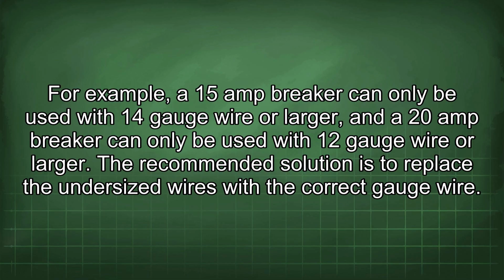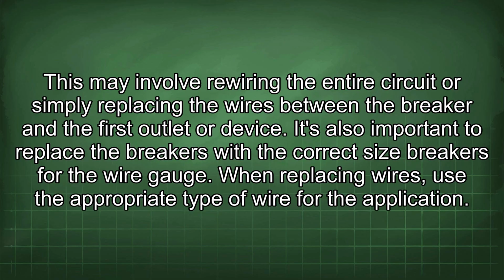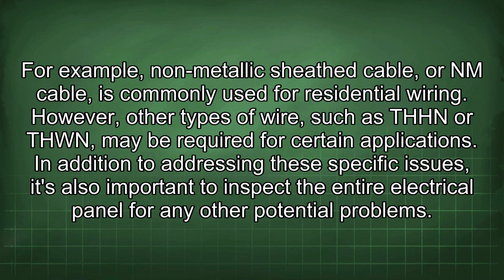The recommended solution is to replace the undersized wires with the correct gauge wire. This may involve rewiring the entire circuit or simply replacing the wires between the breaker and the first outlet or device. It's also important to replace the breakers with the correct size breakers for the wire gauge. When replacing wires, use the appropriate type of wire for the application. For example, non-metallic sheathed cable, or NM cable, is commonly used for residential wiring. However, other types of wire, such as THHN or THWN, may be required for certain applications.